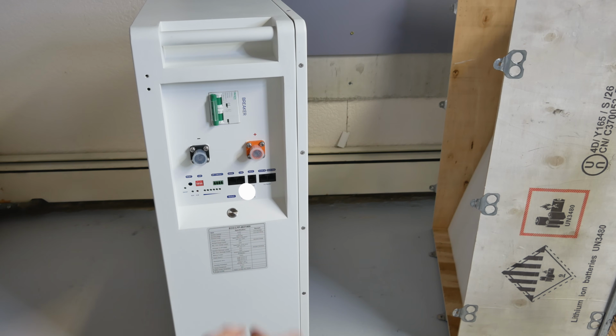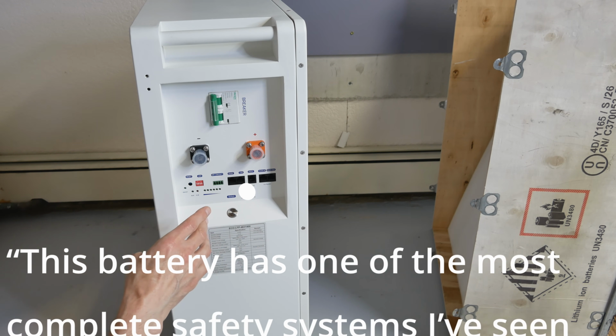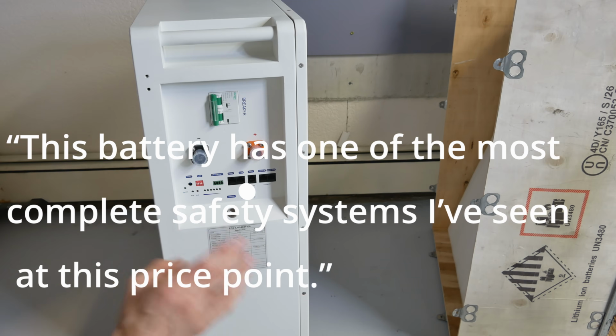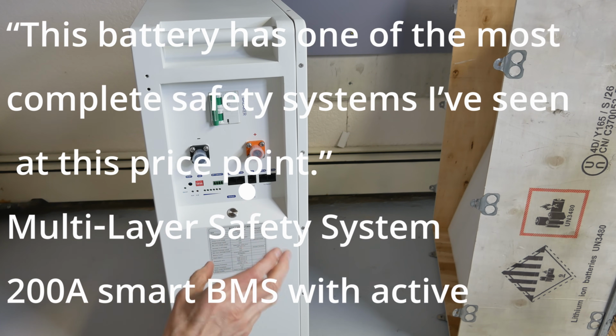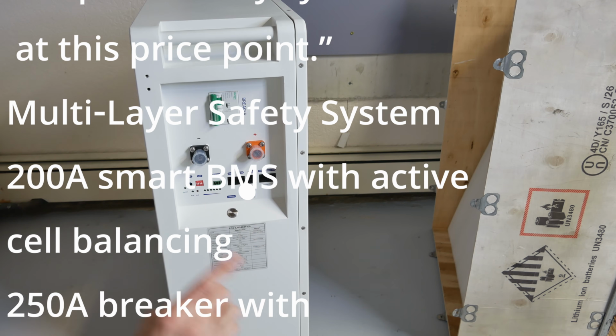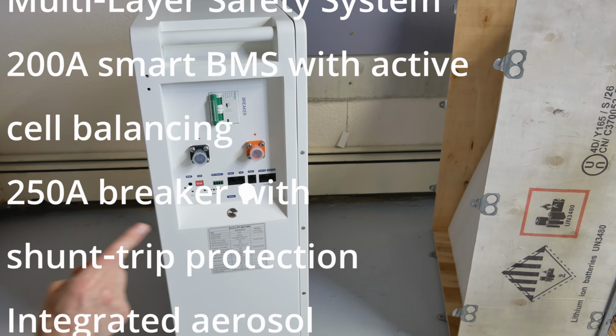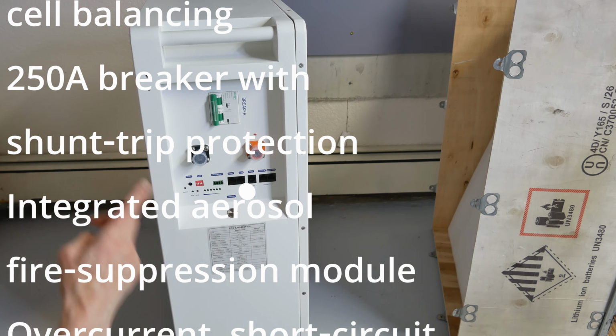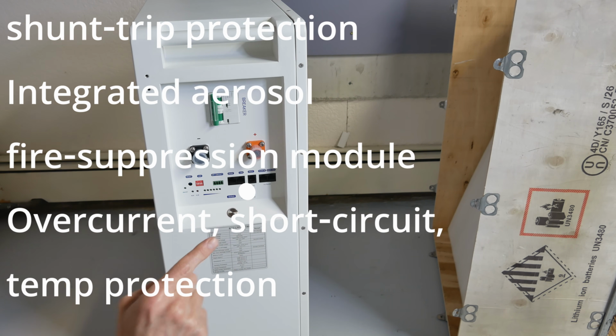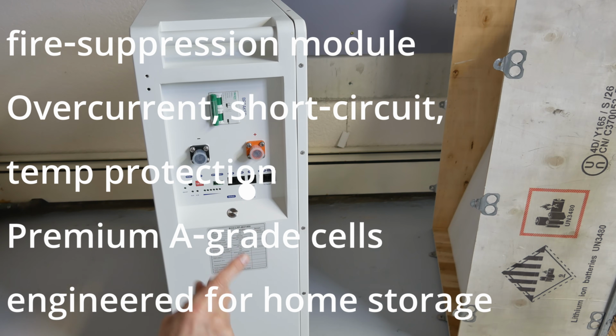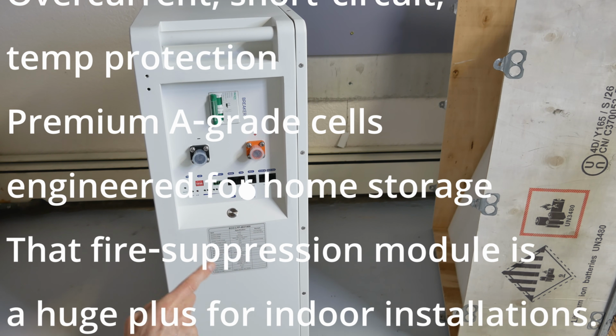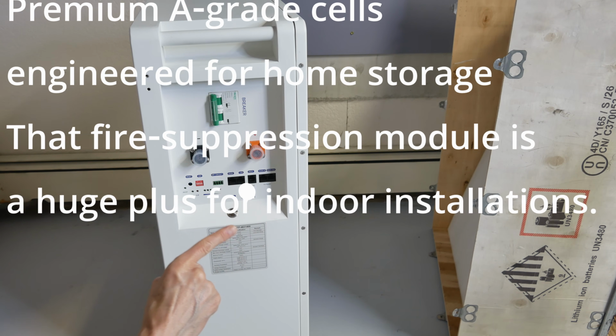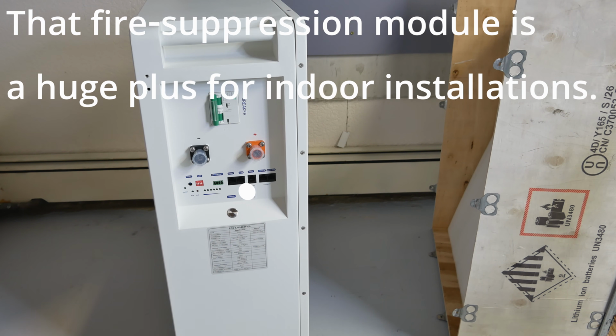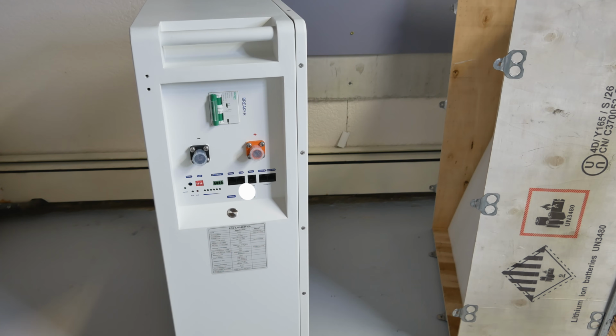Safety and protection for this system - we've got one of the most complete safety systems I've seen at this price point. It's got a multi-layered safety system with a 200 amp smart BMS with active cell balancing, a 250 amp breaker with shunt trip protection. It also has an integrated aerosol fire suppression module in case there's a fire and it can put it out. Overcurrent, short circuit, and temperature protection, and premium grade A cells engineered for home storage. So this fire suppression module inside here is huge for home indoor installations as well.